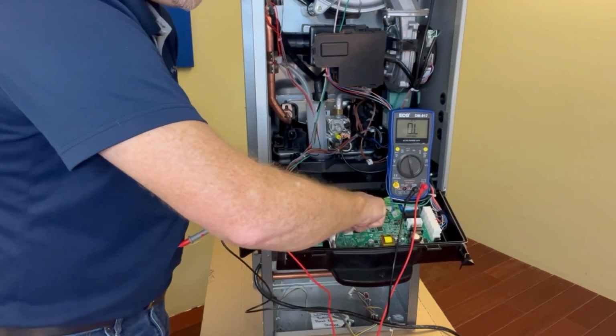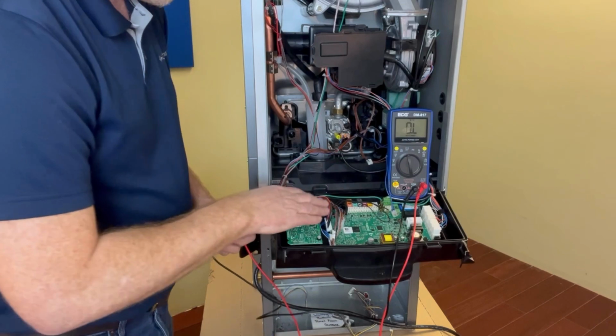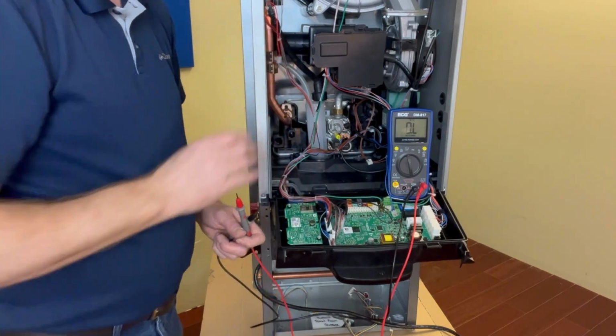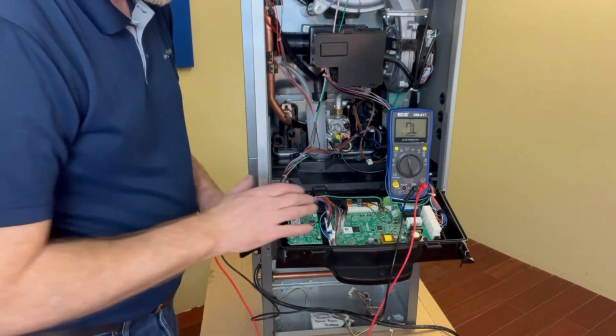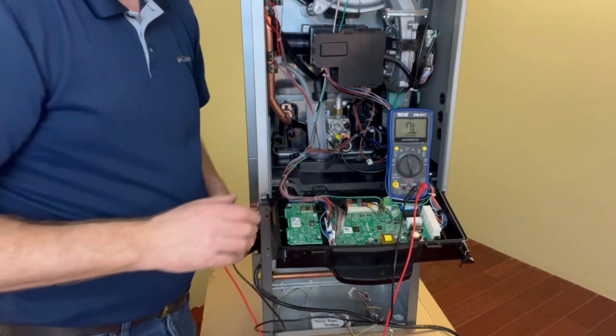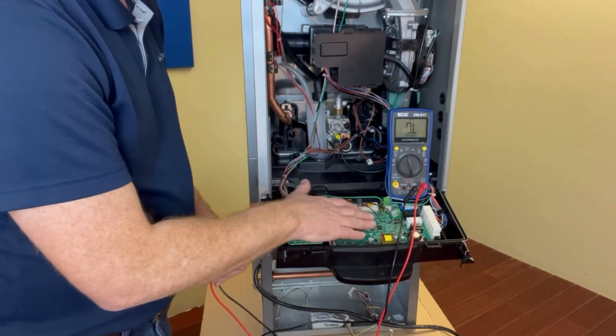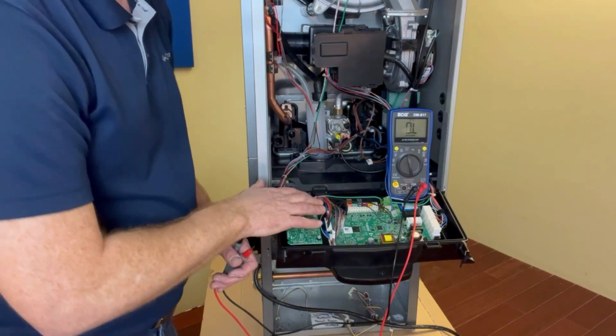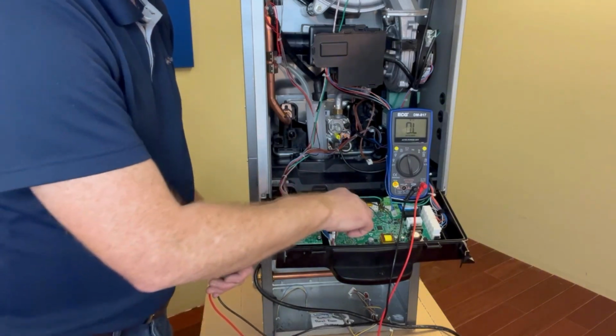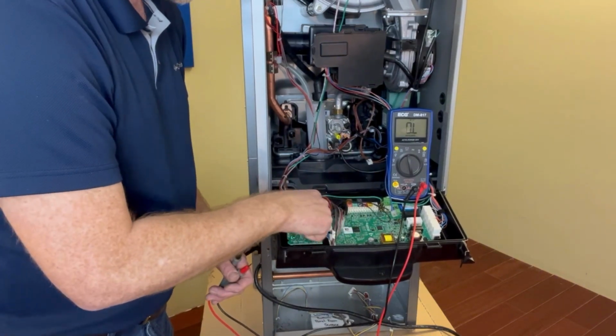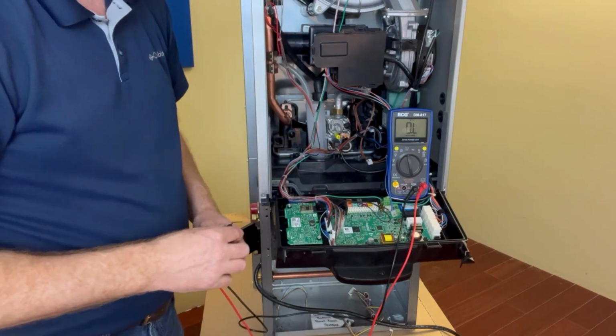Always double check each reading. It's very rare for either the wire harness or the sensor to go bad, especially if there's no water damage. And it's even less common for the circuit board to go bad. So before you condemn a circuit board, make sure you double and triple check each of these wires. We want to make sure that there is no actual problem with the wires or sensors before we start replacing parts.